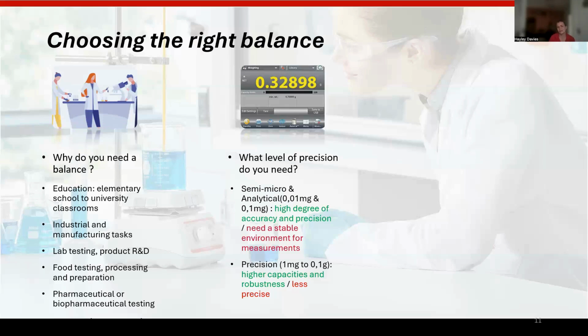Yeah, you can use them if you know that it is a 200 gram calibration weight. As long as you are using the correct class for your balance, it shouldn't really matter if you're using a different brand. Because if you get an external company come in and calibrate your balance, they're not going to have that particular branded calibration weight. They will have their certified calibration weights, and they will use those to calibrate every balance in the lab. So no, you don't need to stick to the same brand. As long as it's the correct classification of weight, and the correct weight according to your balance, you'll be fine. Excellent. Thank you, Hayley.